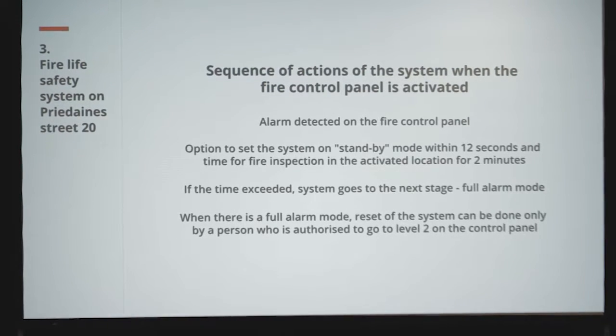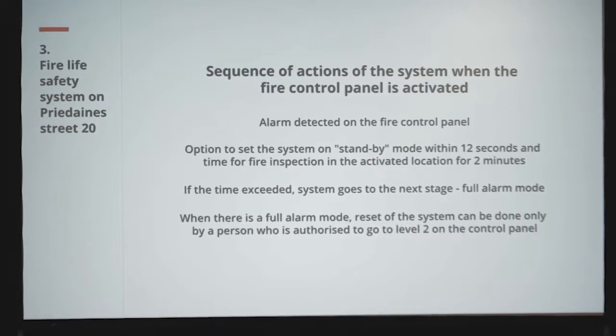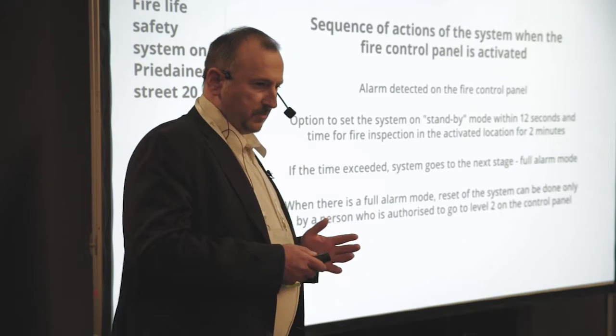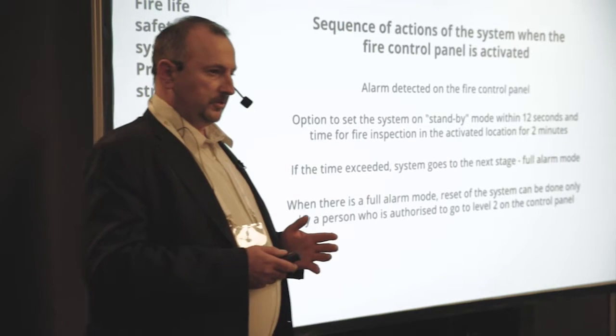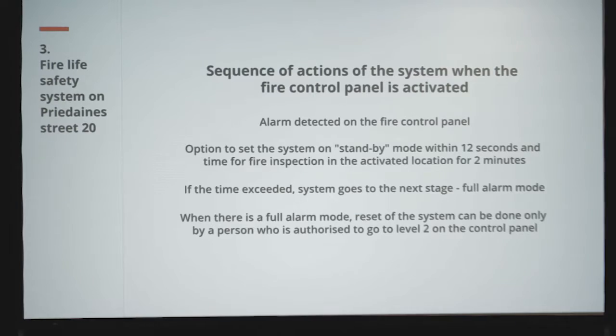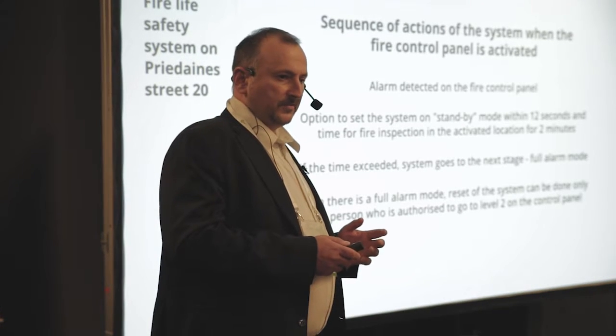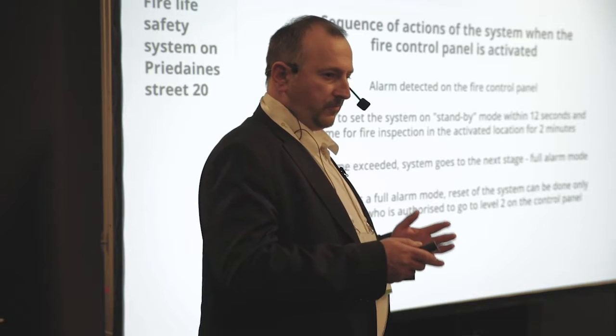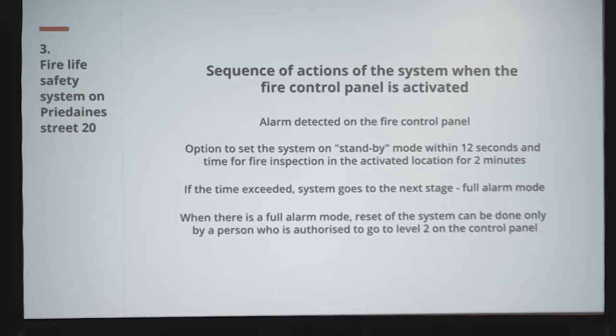What is the normal sequence of such a system? First of all, it's in standby mode. When a fire alarm is coming, then it goes normally into the first fire alarm mode. The system itself checks within 12 seconds if there is a technical false alarm. And if not, if the time is exceeded, it goes into full alarm mode, meaning the second fire alarm step.